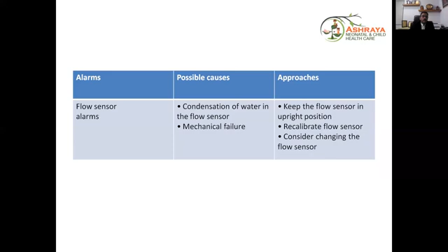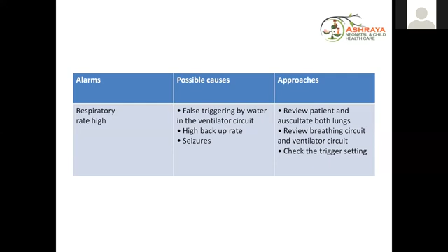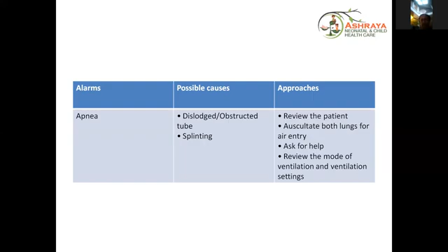Respiratory rate high: the possible causes are false triggering by water in the ventilator circuit, a high backup rate, and there could be seizures. The approaches are: review the patient and auscultate both lungs, review the breathing circuit and the ventilator circuit, and check the trigger settings. Apneas could be because of a dislodged or obstructed tube or splinting. Again, see the patient and auscultate both lungs, ask for help, and review the mode of ventilation and the ventilator settings.